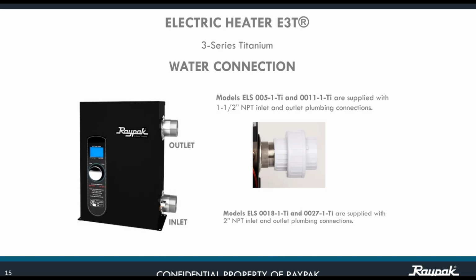Proper water flow through the unit is critical. So in the 5.5 and the 11 kilowatt, we have 1-1/2" NPT inlet and outlet connections, and that is going to allow us a max flow of 50 gallons per minute at 8 feet per second. Think about this. You need to have proper flow, but also proper velocity. If you go too fast on the velocity, chances are that the heat exchanging we are supposed to be doing in that chamber with the elements is not going to happen. It's just going to be water passing through the elements, but the cold water coming from the pool never is going to pick up the heat from the elements.